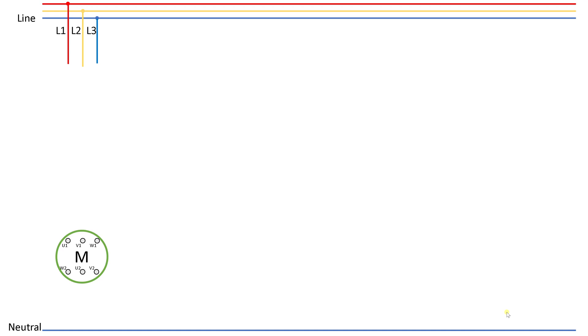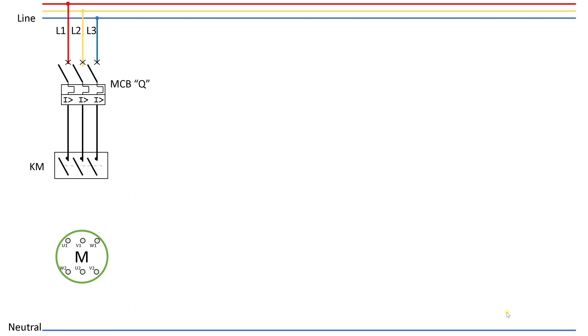Welcome back. You know the concept behind the star-delta circuit and which motor we can connect it to. Now we will study the star-delta power circuit, and in the next lecture we will look at the control circuit. For the power circuit, we put our MCB, then our contactor, then our overload relay. We need to connect our motor in star first and then shift to delta, and to do this we will use contactors.